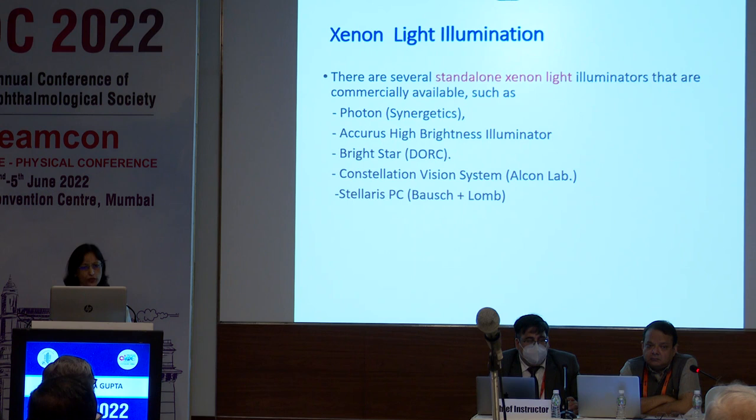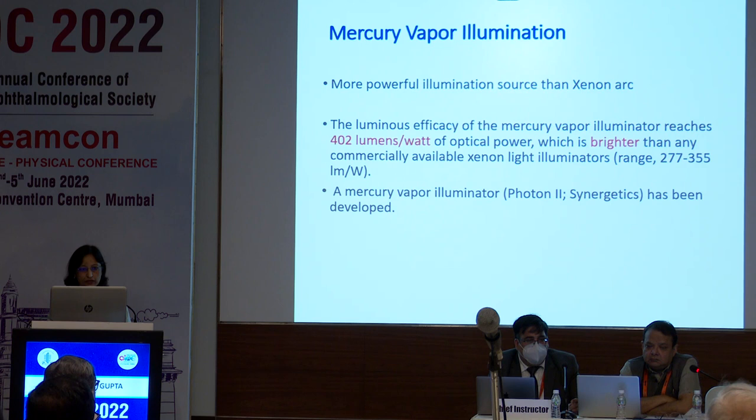There are various standalone xenon light illuminators that are commercially available, like Photon, Accurus, Brightstar, Constellation Vision Systems, Stellaris PC. Mercury vapor illuminators are a much better and brighter source, with luminous efficacy reaching up to 402 lumens per watt, which is brighter than any commercially available xenon light illuminator.